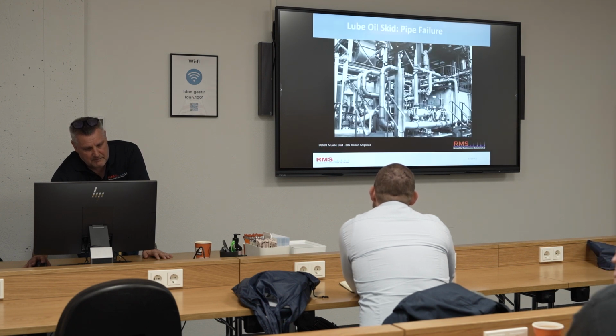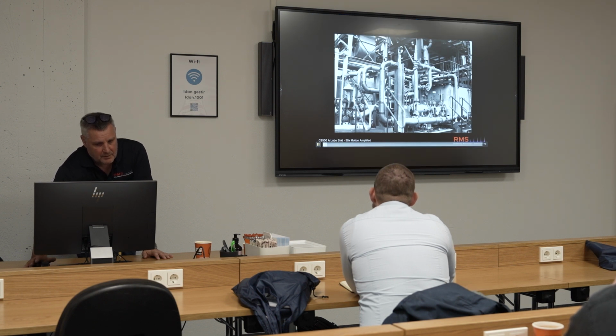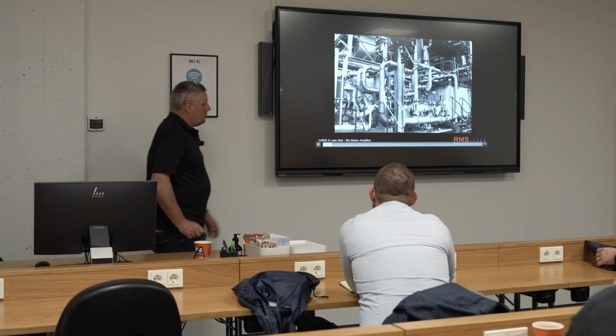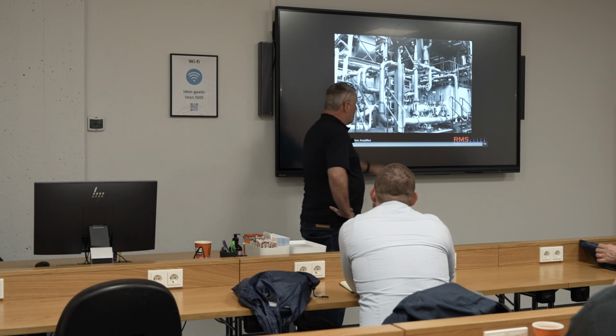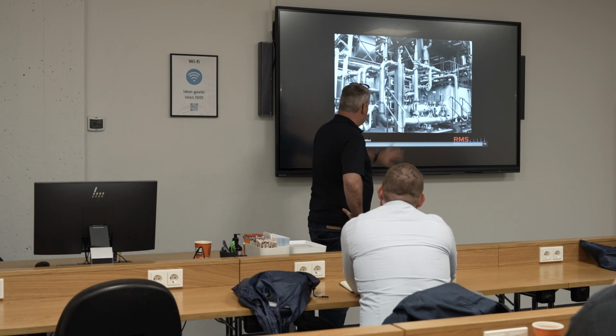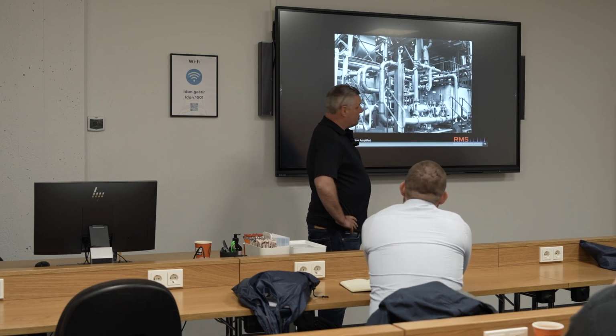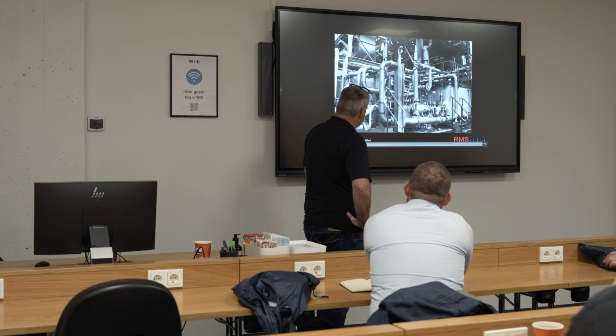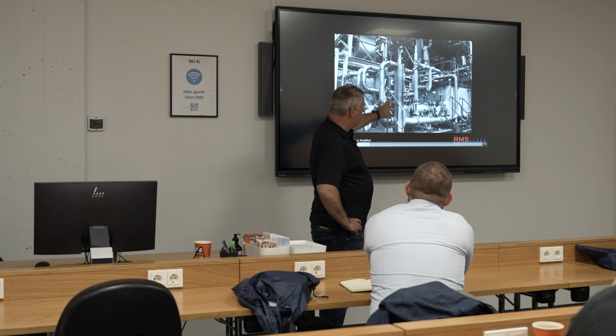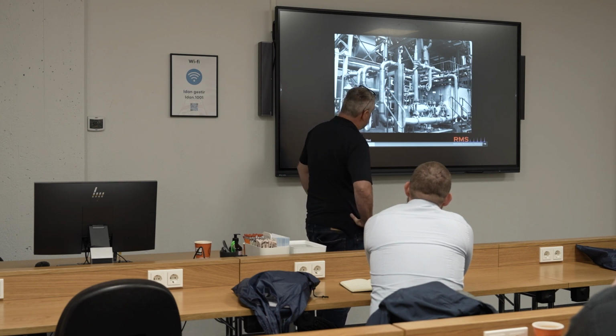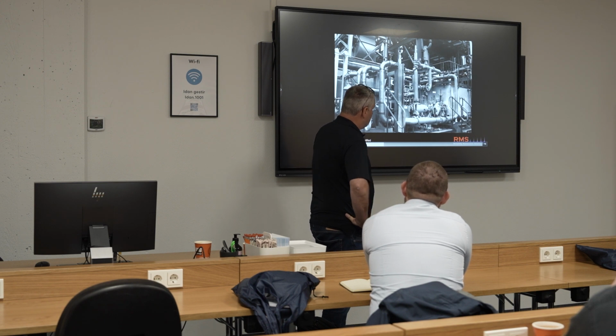Lube oil skid pipe failure. This was actually a situation where the pipe let go. We're monitoring this because they've got piping issues here, and you'll see this for yourself. This is genuine as well. This is amplified and they've got an issue here. They've had issues for a while, but they can see a little bit of movement visually here. And this is, again, Stuart's job. He's not very lucky, Stu. You can see this pipe work is going to go.